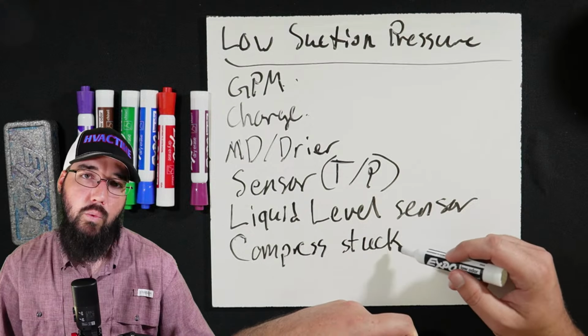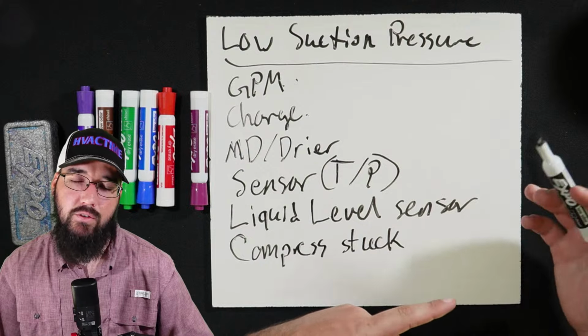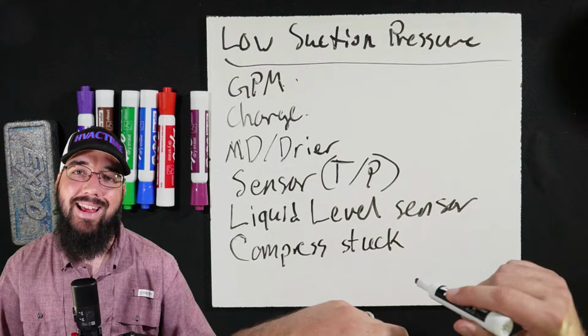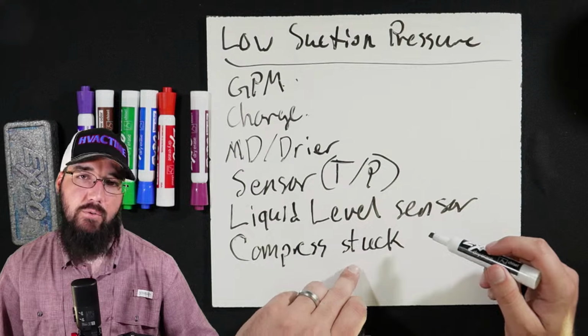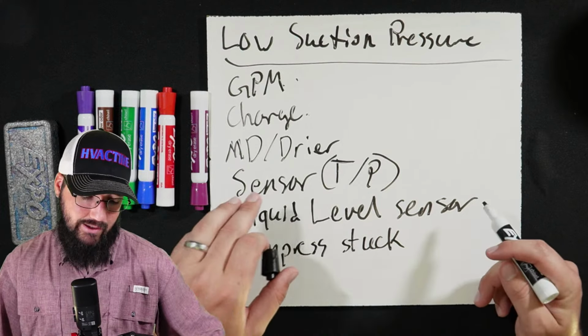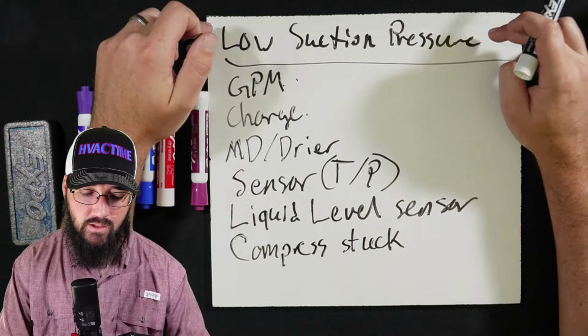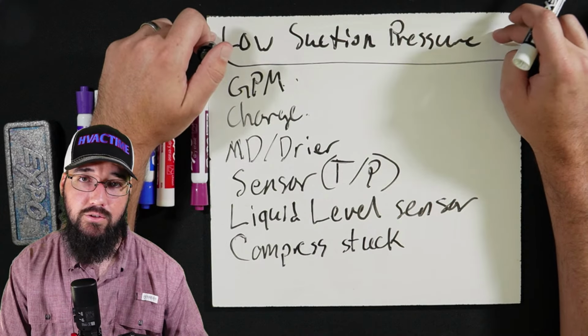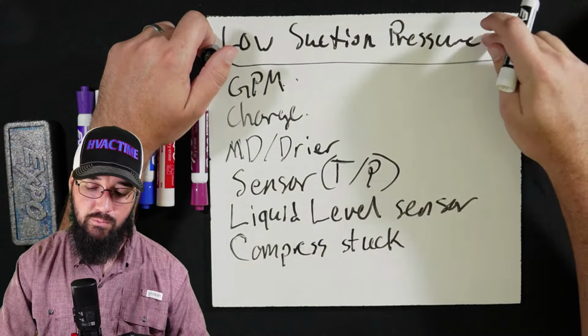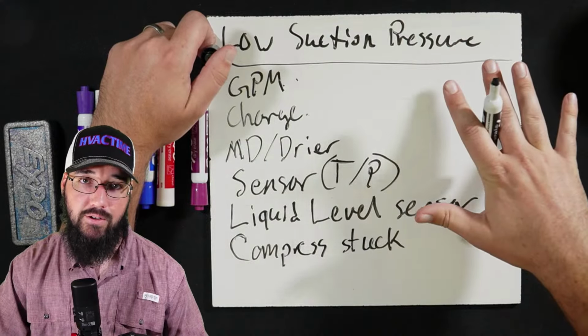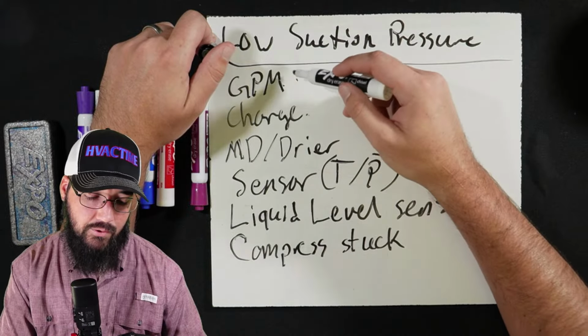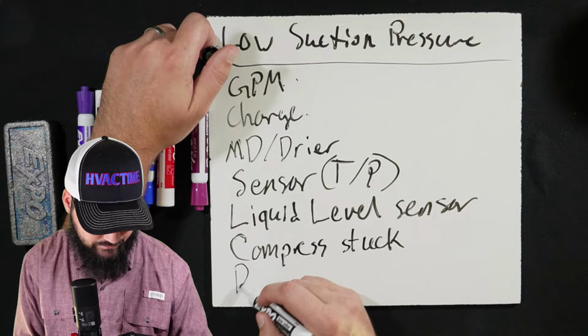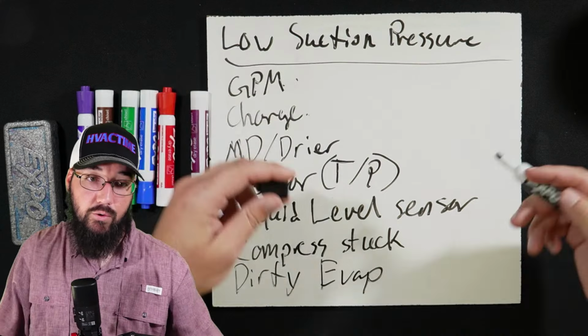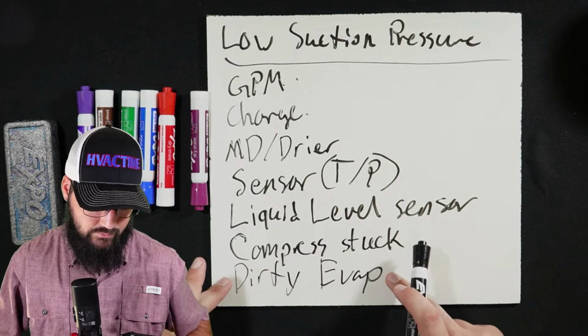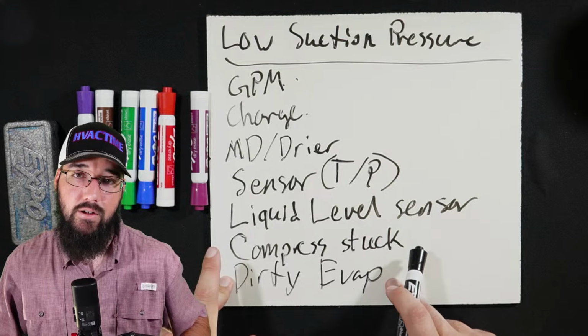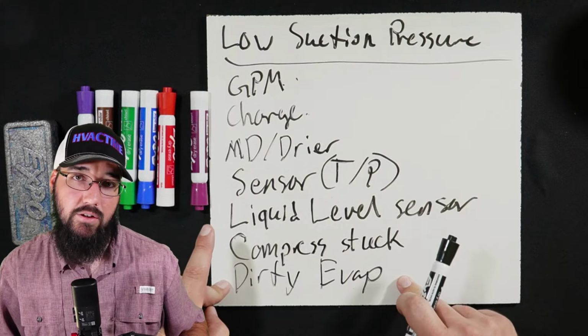You also, depending on where it gets stuck, may have issues where, every once in a while, it trips on a motor overcurrent or something like that at startup. That could be another indication that the slide valve is not working correctly. And if the slide valve is stuck in a loaded position, then that could cause a low suction pressure to show up as the machine gets the loop load down. So this will be a result of over processing the loop, forcing our saturation down heavily. That could be part of our issue. Other than GPM, though, we could have a dirty evaporator. This is an old enough machine, being an RTAC, that we could just have junk, silt, whatever, in the evaporator. And so you may not have a GPM issue, you just can't make heat exchange. That's another thing to consider.